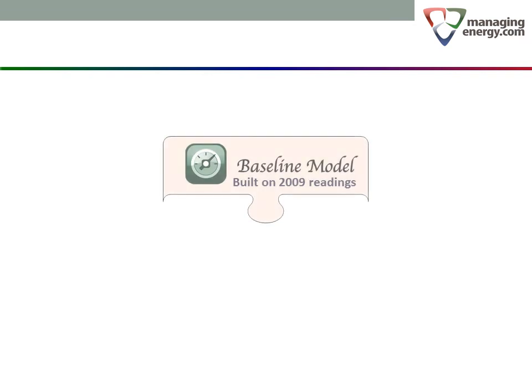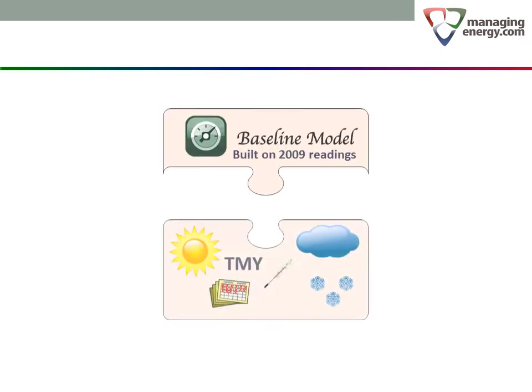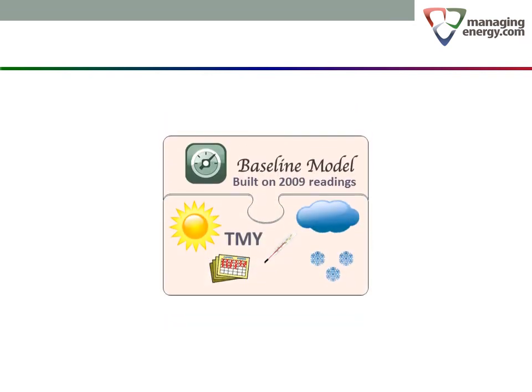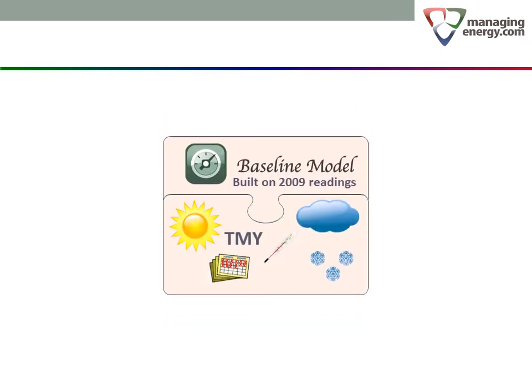To get a typical year fixed baseline, produce the model for the base period in a standard way. Then gather the TMY data for the weather station. The resulting combination is a baseline value representing a typical year at the building location. It is also the best basis for predicting future consumption. Our fixed baseline consumption will be what we would expect to consume if the building performed exactly as it did during the baseline period and we had absolutely typical weather.